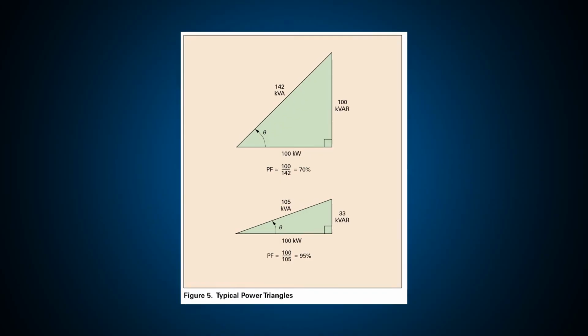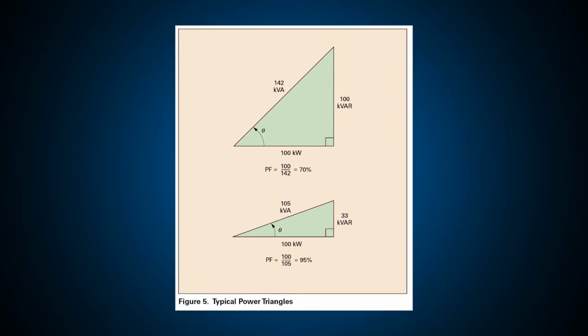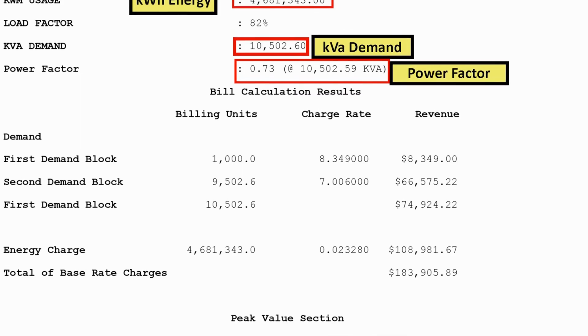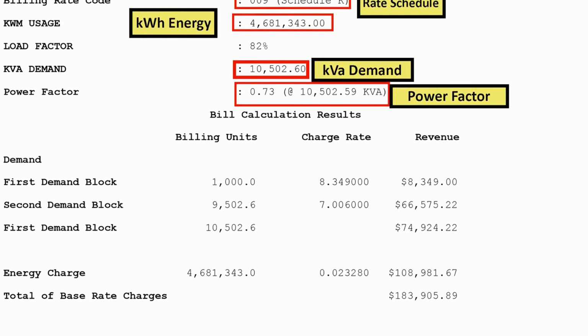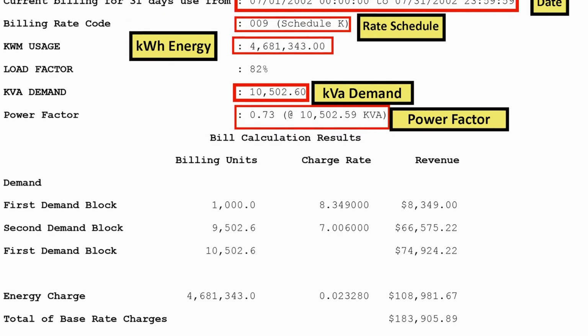Here at the Power Systems Experience Center, we've done the calculations, we've done the measurements, we've talked to the vendors. We simply do not believe the excessive claims. Can you save money with power factor correction? Yes, if you're a large utility customer and you have a power factor penalty, but certainly not for a homeowner. Again, it's not that capacitors don't work for their intended purpose of power factor correction, but they're not energy savers. In addition, putting capacitors in your system without proper analysis and sizing can be problematic, resulting in voltage and harmonic issues. There are plenty of other examples of vendors exaggerating savings.